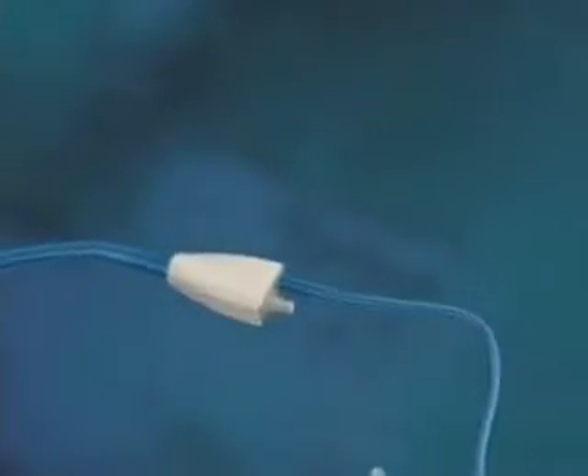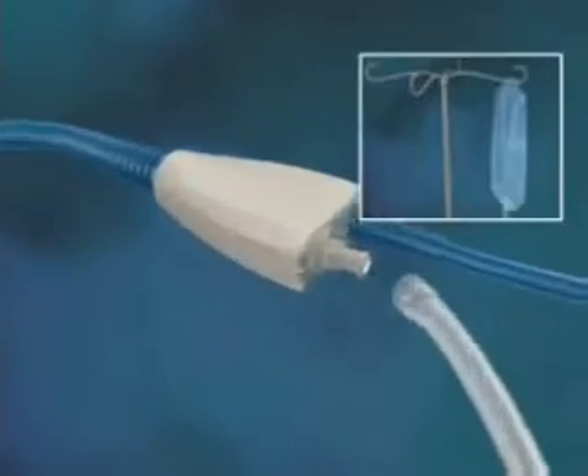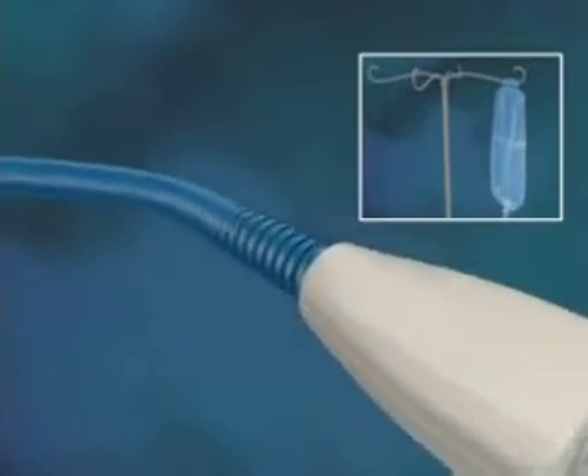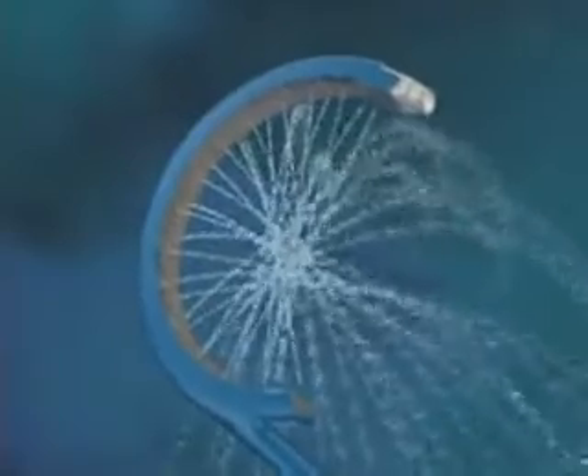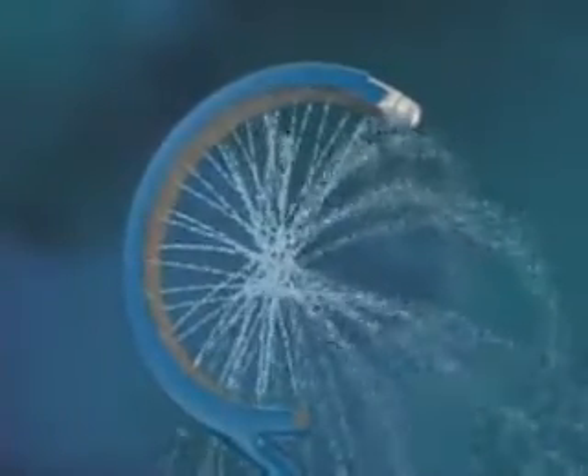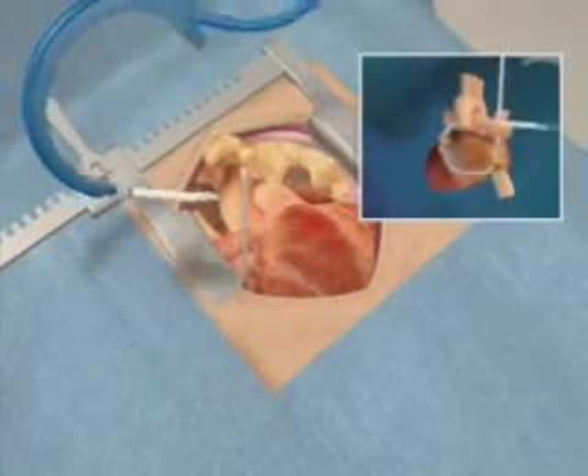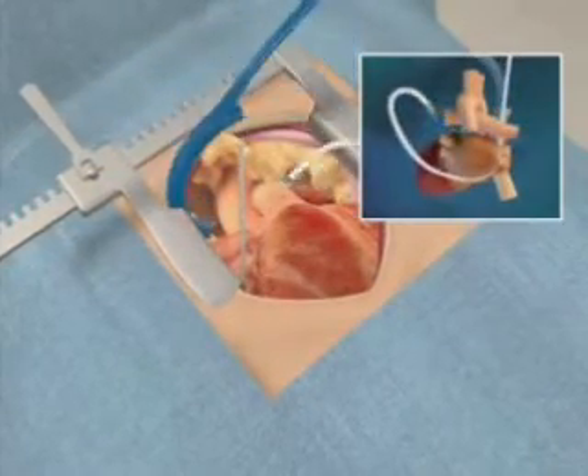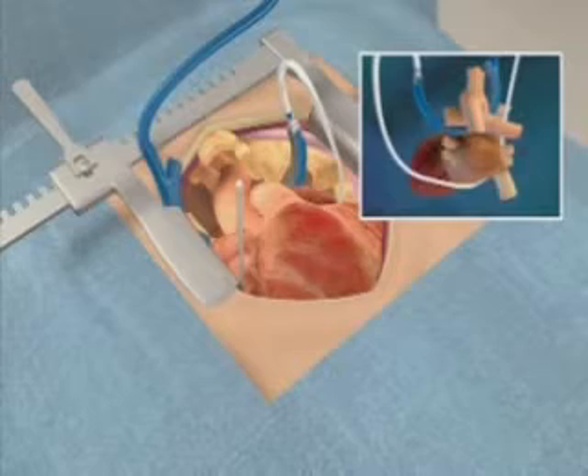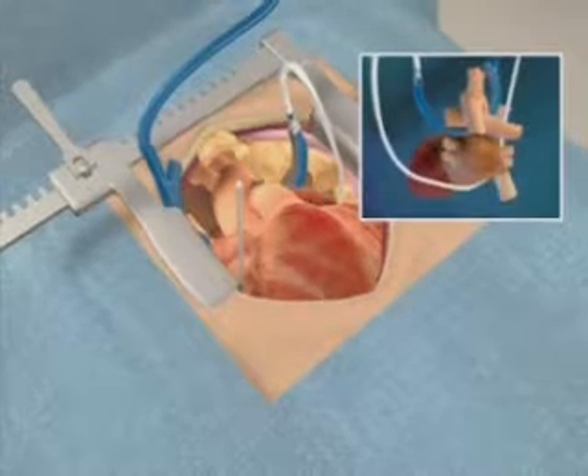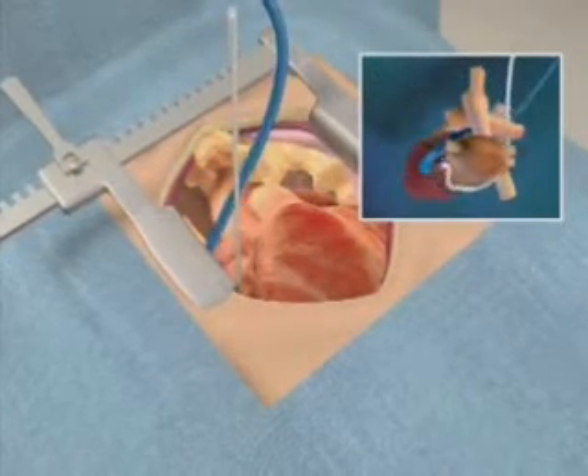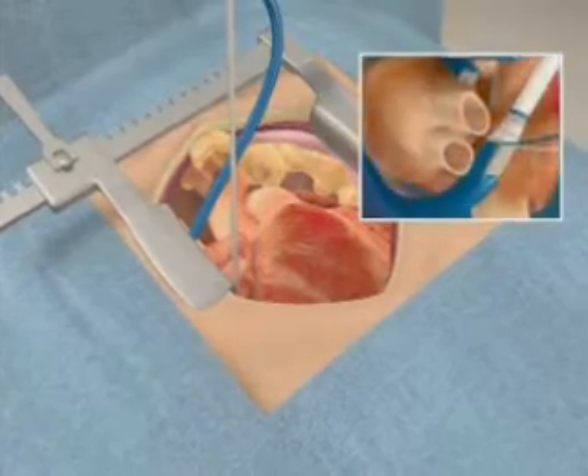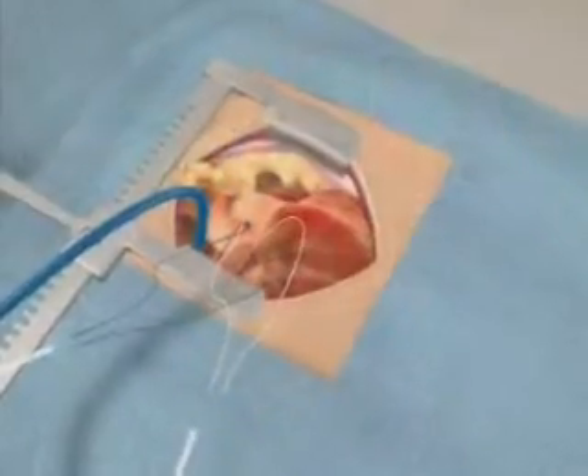After the appropriate size UltraCinch is selected, it is primed with room temperature normal saline. Priming the device improves coupling of the membrane to the tissue and also cools the tissue surface during ablation. After priming the device, the UltraCinch is then attached to the positioning and sizing system. Using the positioning and sizing system, the surgeon then places the UltraCinch into position around the left atrium.